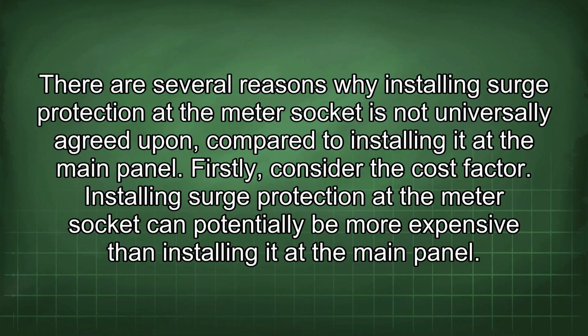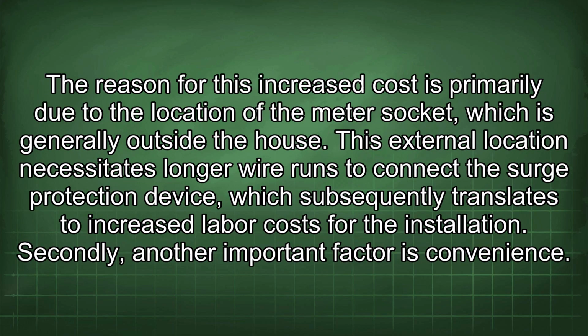There are several reasons why installing surge protection at the meter socket is not universally agreed upon, compared to installing it at the main panel. Firstly, consider the cost factor. Installing surge protection at the meter socket can potentially be more expensive than installing it at the main panel. The reason for this increased cost is primarily due to the location of the meter socket, which is generally outside the house. This external location necessitates longer wire runs to connect the surge protection device, which subsequently translates to increased labor costs for the installation.